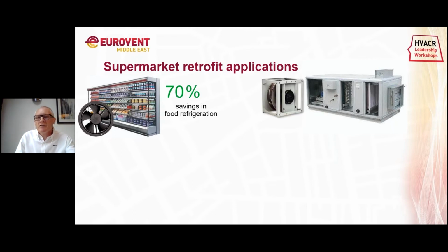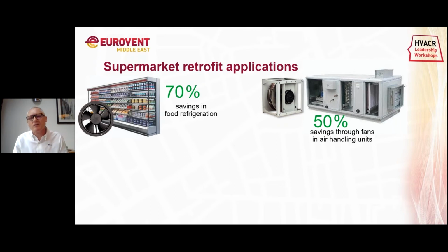When you look at air handling units, most supermarkets will have air handling units of some type. Just by taking out a belt-driven fan without an inverter and putting in a plug fan with an EC fan, you're looking at potentially 50% savings. Now, this is not always the case. Sometimes we have seen up to 70-80% savings on some air handlers if we manage to adjust the speed, the airflows and the velocity. But on average, we see about 50%.